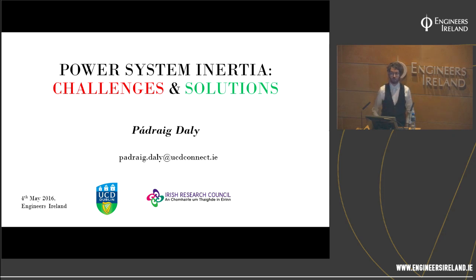It can be done, and it will. I suppose one of the reasons I put up the demand response there is that what's going to be very important when we move forward is that we control the thing. We control our responses. So, for example, at the moment, we have demand response, but all that involves is tripping loads. Now, it gets to a point where you can't just trip the loads and forget about it. You need to control that tripping so that you move with the frequency.